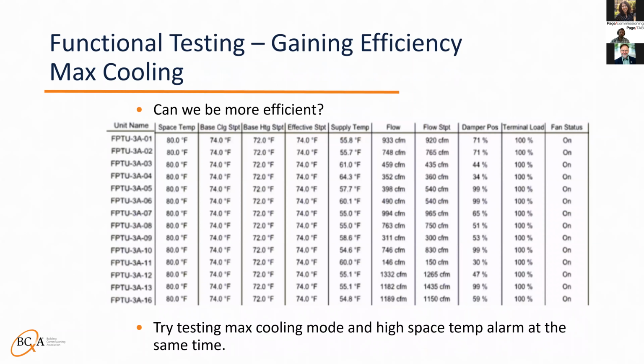So can we be more efficient than just testing the alarms at one time? Why not test max cooling while testing the high space temp alarms? All the high alarms will be tripped at the same time, and you can quickly click through the sample of boxes to verify the alarms appear on the graphics. Placing all the boxes in full cooling at one time will help to be more efficient, but it will also help to check for TAB issues. For example, this image shows series fan-powered terminal units with the space temperature overridden to 80 degrees to drive all boxes to full cooling. Once everything has settled out, review the list for issues.